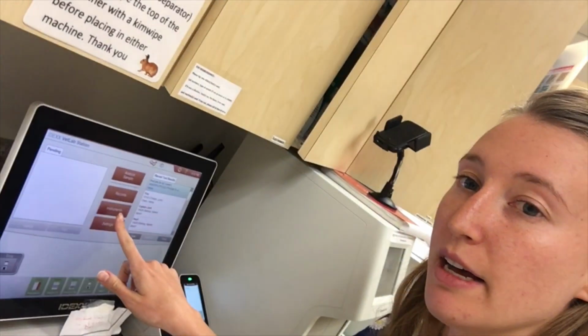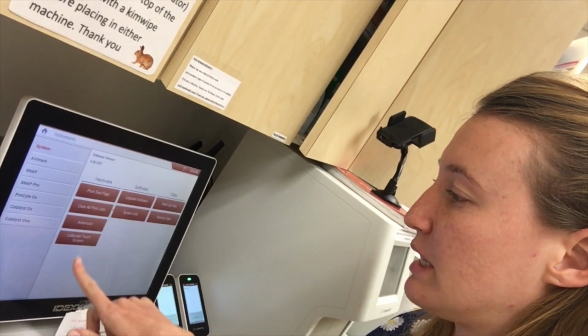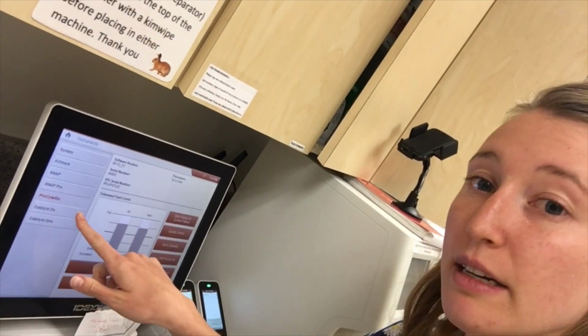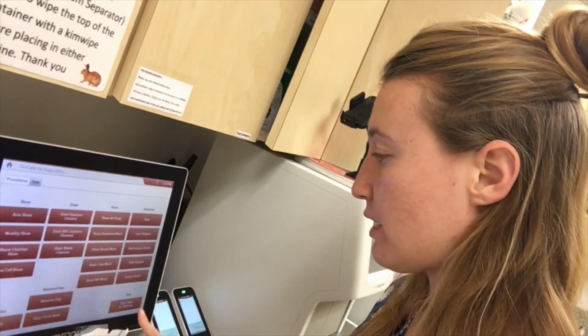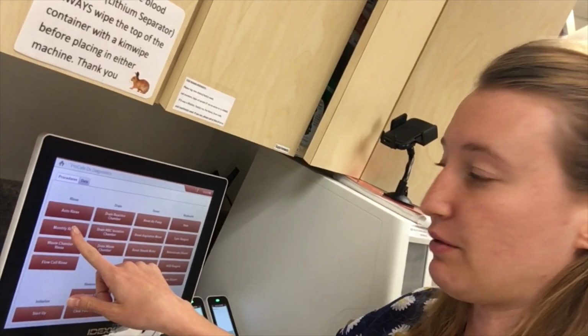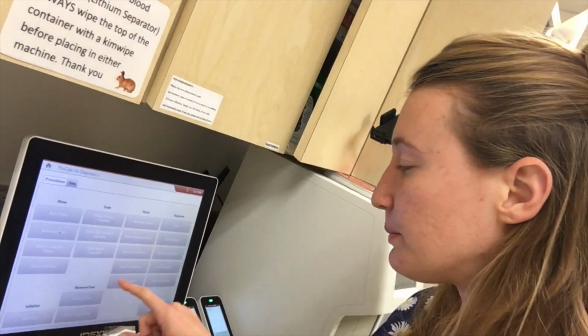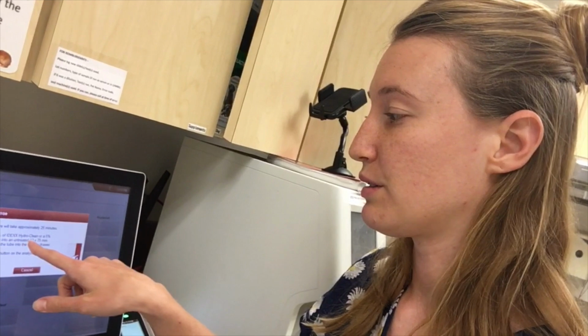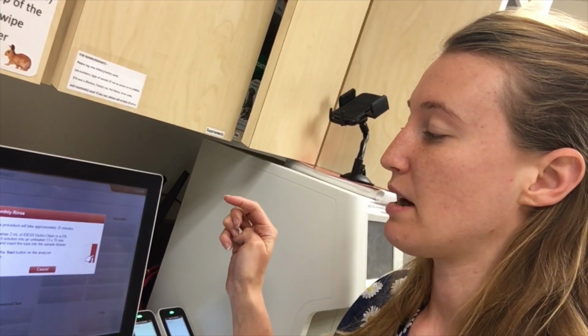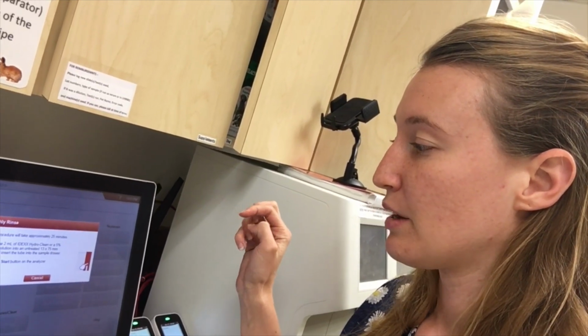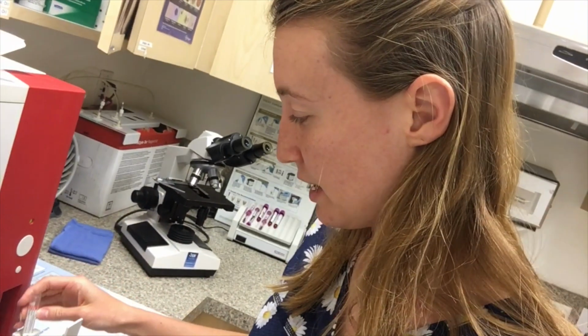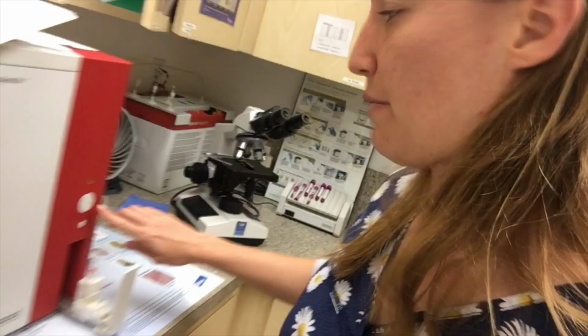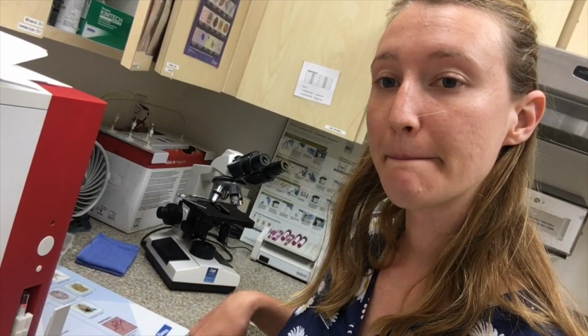Okay, so now I'm going to perform the monthly rinse on the IDEXX ProCyte machine, which is the CBC machine. I am going to click instruments on the vet lab station. I'm going to do the ProCyte instrument, and then diagnostics, and then I'm going to look for monthly rinse. And so I'm going to click monthly rinse. This one gives you the option of the 2 ml of the HydroClean or 5% bleach solution. I've already made a bleach solution, so I am going to put bleach solution in an untreated container. I'm going to push the start button, and now it's going to do its monthly rinse.